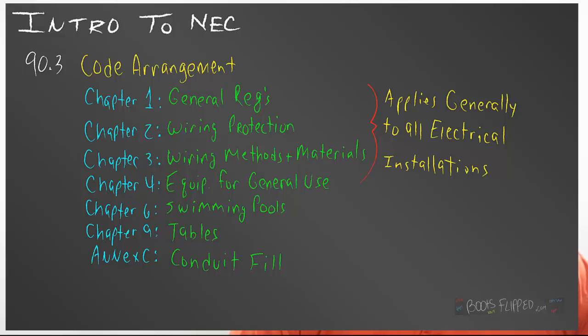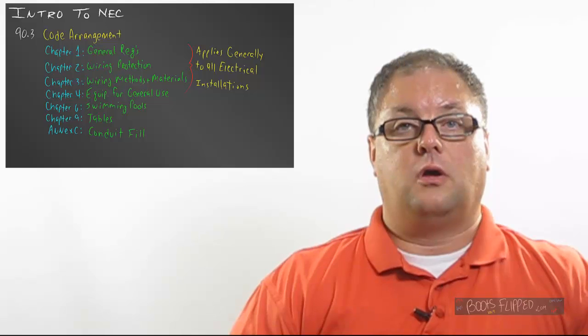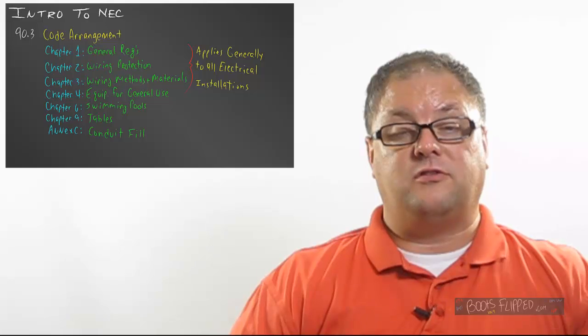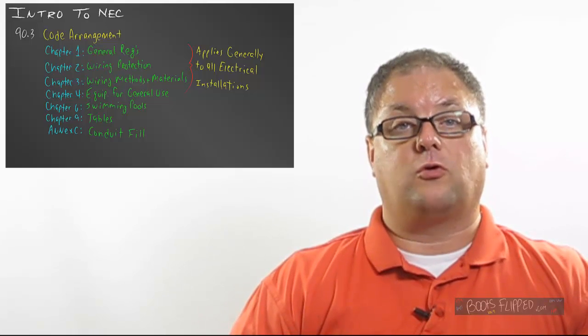Chapter three is wiring methods, and there's a lot of stuff in there — especially Table 310-15B-16. That is our go-to number one table that we're always looking at, and that's where you're going to hear me talk about the 60-degree, 75-degree, 90-degree table. Chapter four is equipment for general use — lights, motors, all kinds of things in that chapter for residential. All four of those chapters put together generally apply to all electrical installations, so no matter what kind of wiring you get into as an electrician, you're going to be going through chapters one through four quite a bit.